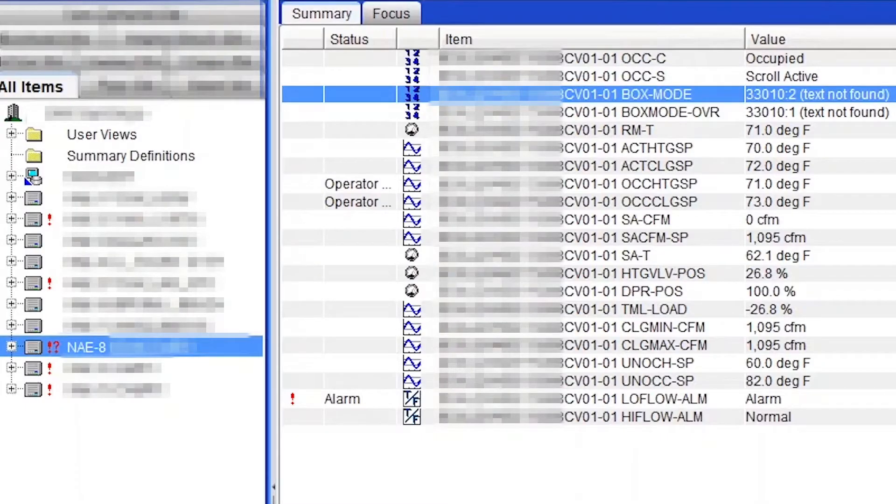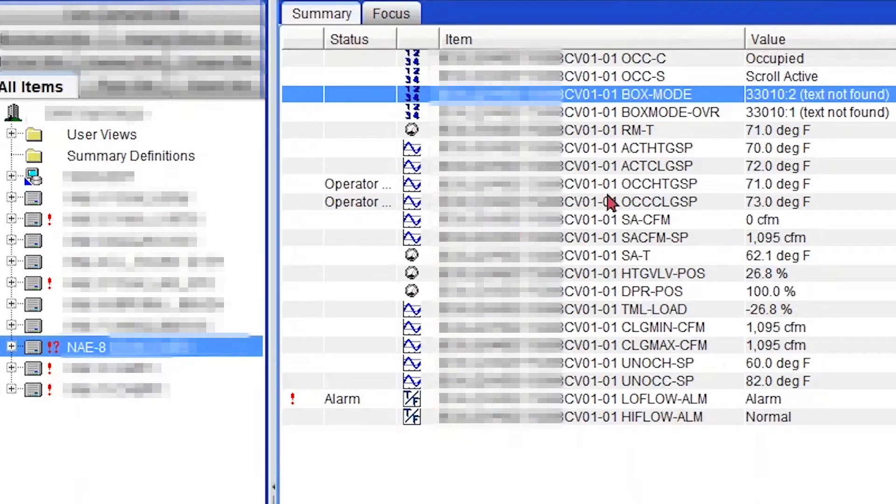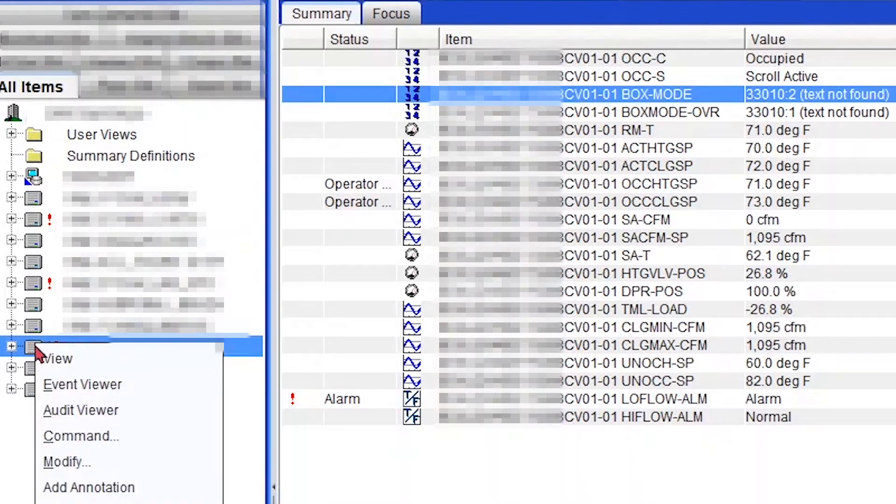Okay, so this is how you fix it. You're going to go to your network engine like NAE or NCE, right click on it, and then go to Command, then select Rediscover Text Strings, and then send the command.